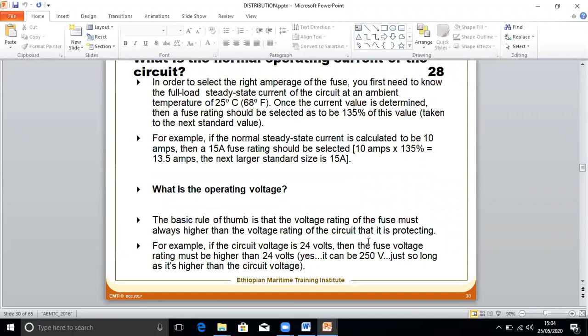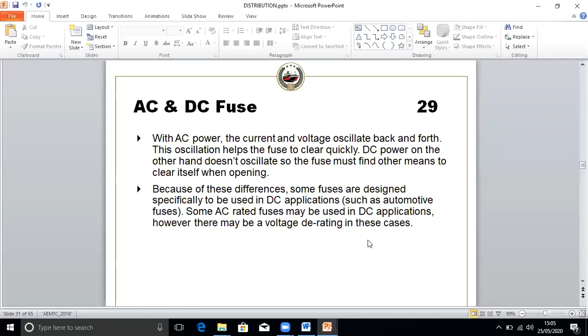AC and DC fuse: can we use an AC fuse and a DC fuse interchangeably? See, in AC power, the current and voltage oscillate back and forth. The oscillation helps the fuse to clear quickly. In DC, on the other hand, it does not oscillate. So some fuses are designed only for DC applications, like automotive, and some AC rated fuses may be used in DC applications. So this is the importance of it. Some DC fuses are specifically only for DC applications. You can use only that fuse in that case.